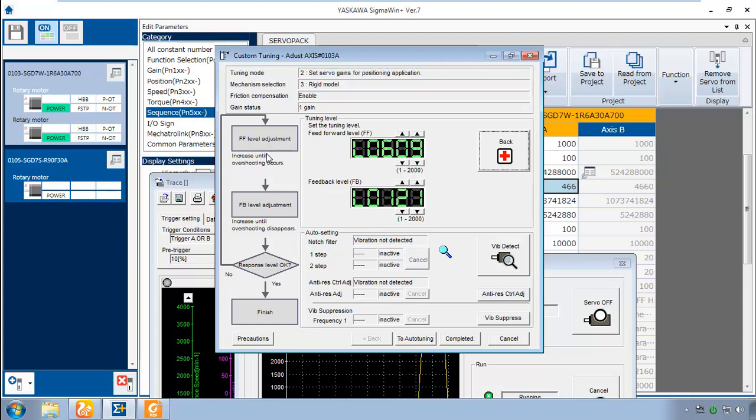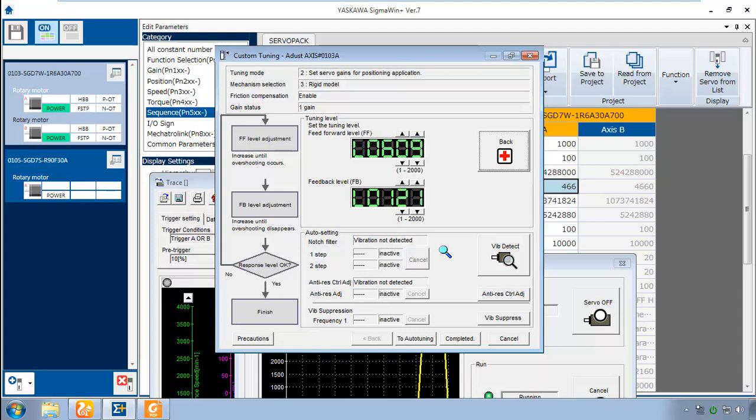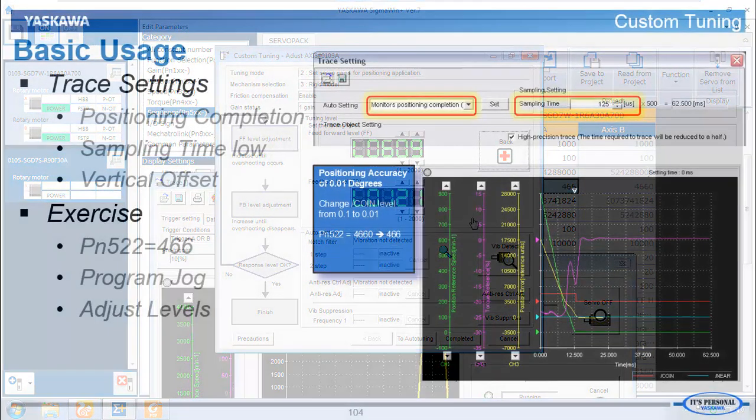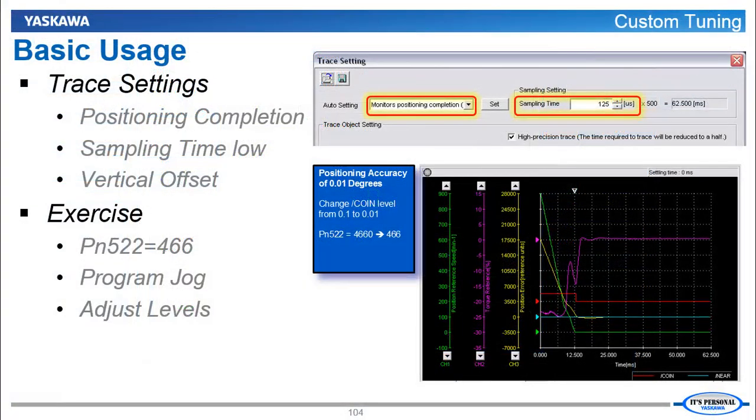The flow chart gives an idea of what to do. It says increase feed forward until overshooting occurs, then increase feedback until overshooting disappears. And when the response is OK, you are finished. And at the same time as you're increasing the response, sometimes you will need a notch filter or anti-resonance or vibration suppression filter to cancel out a mechanical resonance that previously had not been revealed with the lower response.